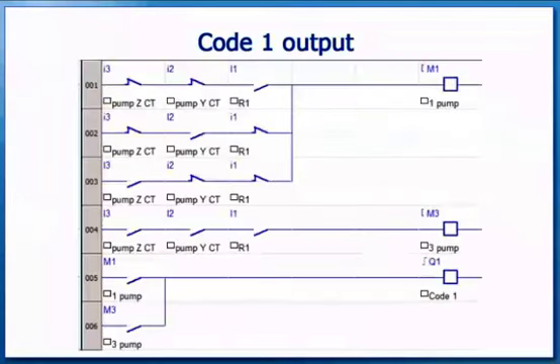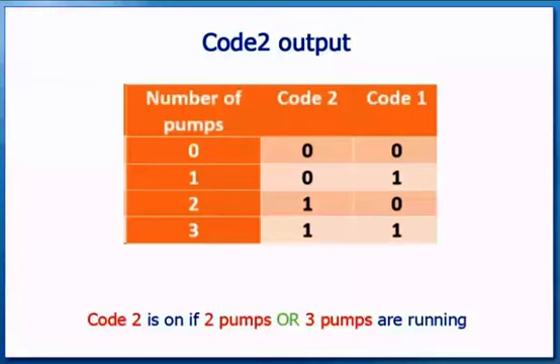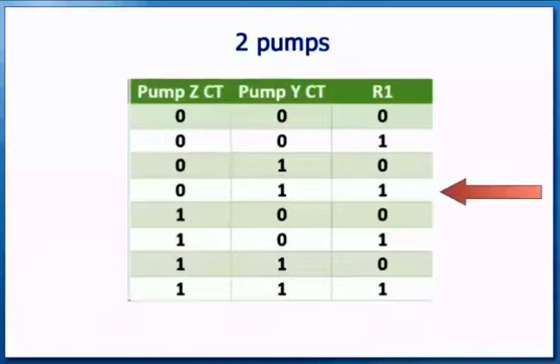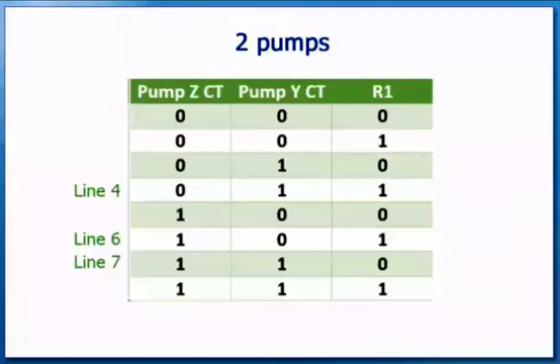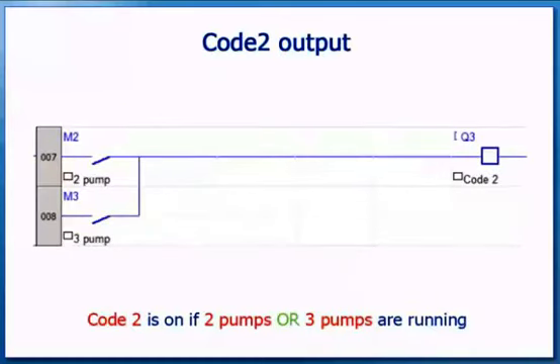We can now put it all together to show the complete program for turning on the Code 1 output. The next section to develop is the Code 2 output. Code 2 comes on if there are two pumps or three pumps running. We need an internal relay for two pumps. Here is the truth table showing all pump combinations — identify which ones occur for two pumps running. Go ahead and produce the program for the two pumps relay, then combine the two pumps and three pumps relays to turn on the Code 2 output.